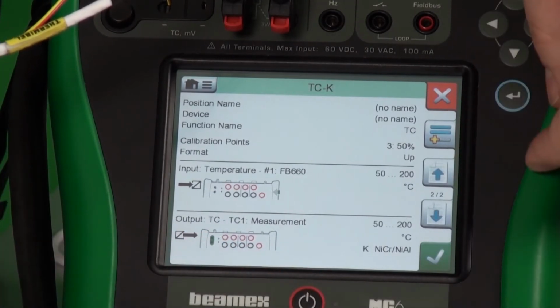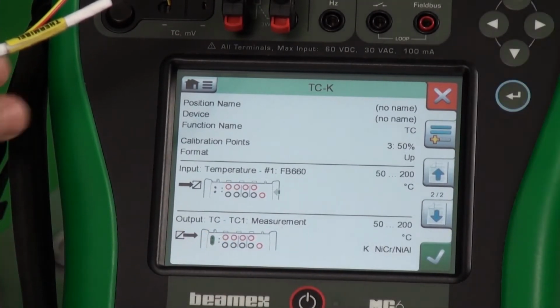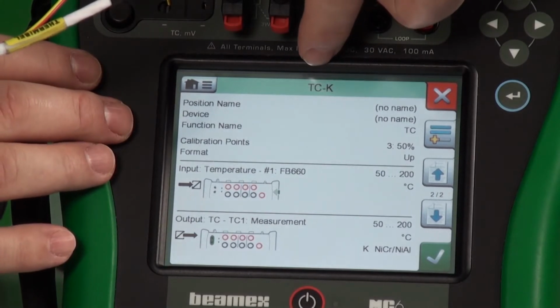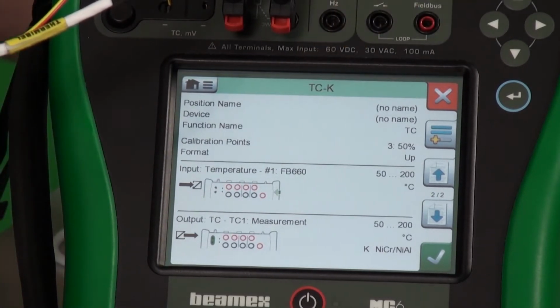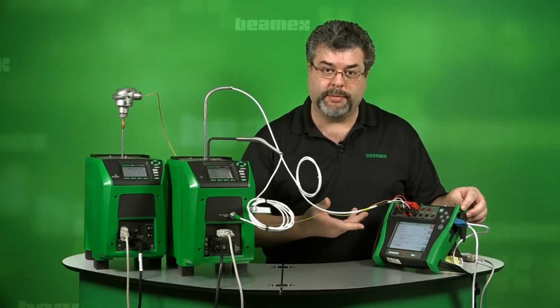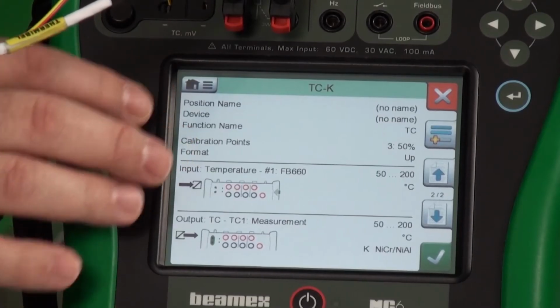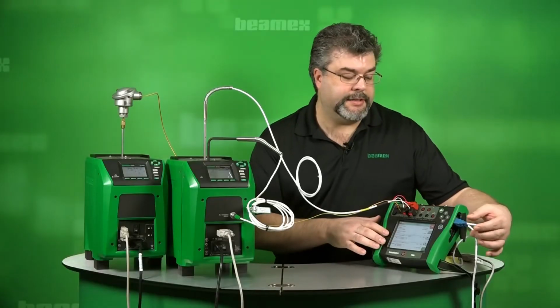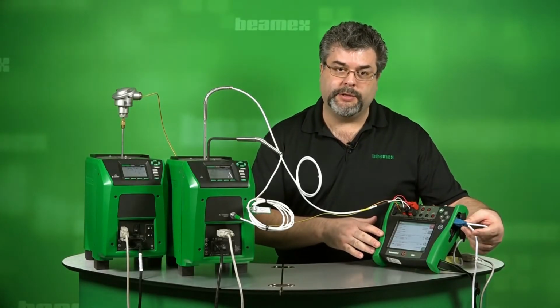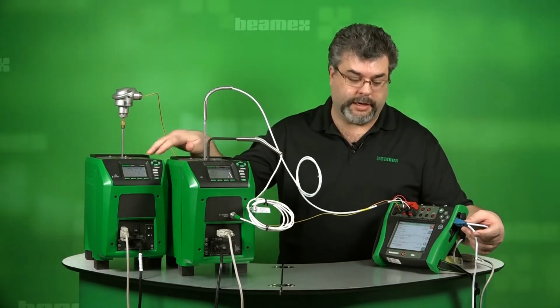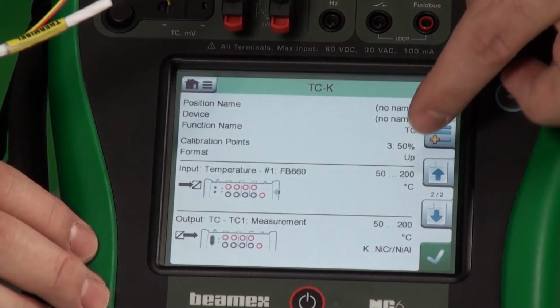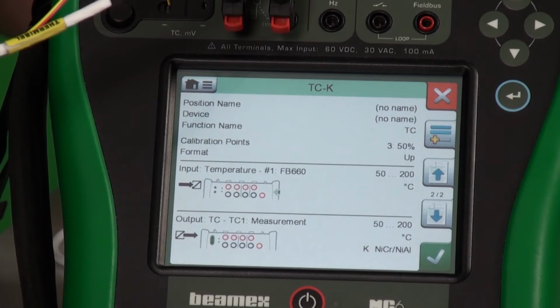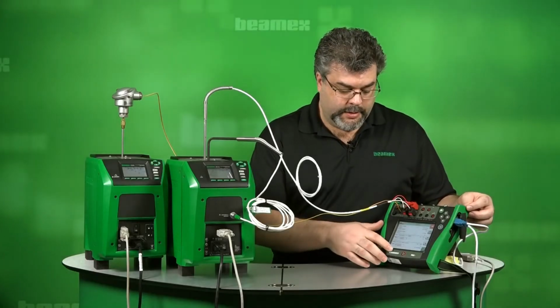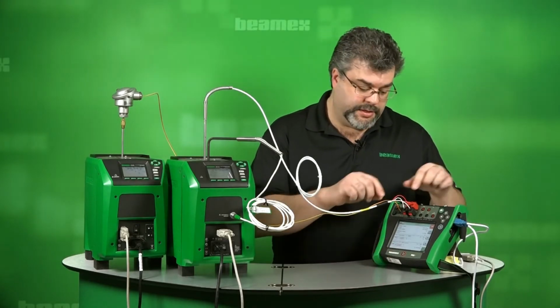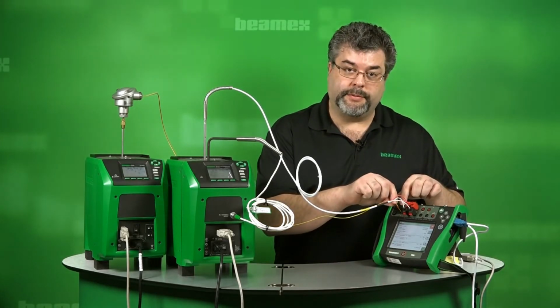Let me go down to the next one. The next test is our thermocouple. Now in the same way, you can see the tag name across the top, and we just called it TC-K to make it obvious. It's a K-type thermocouple. We have our position name, we have our input here. Again, it's telling us we need to hook up to the side USB to connect to the other dry block. And the range is set for 50 to 200 degrees Celsius, and that's for the input and the output. It shows us as well that we're using this set of terminals to measure the thermocouple.